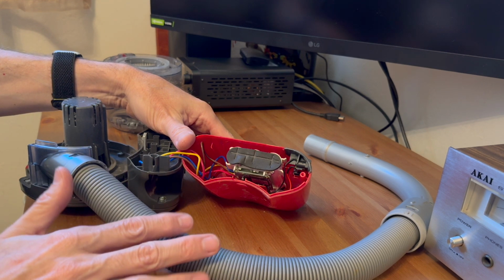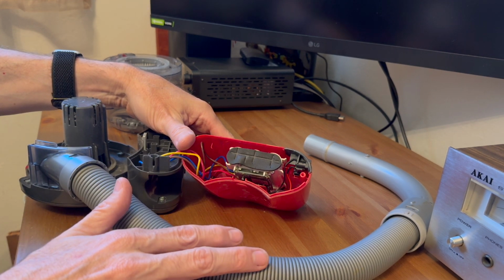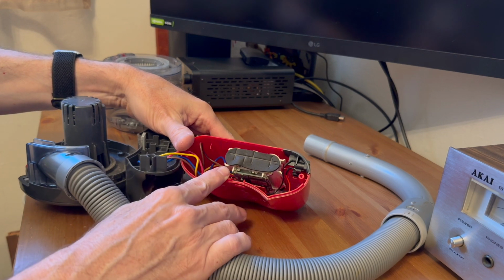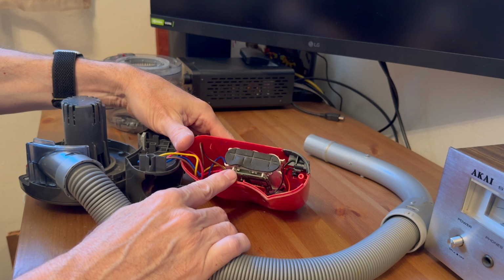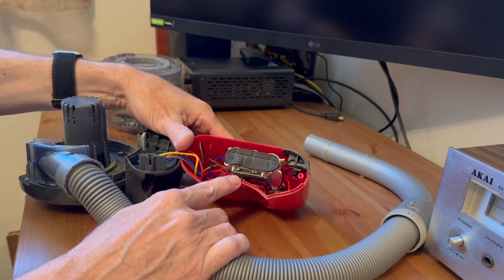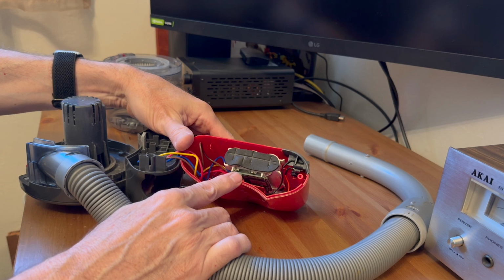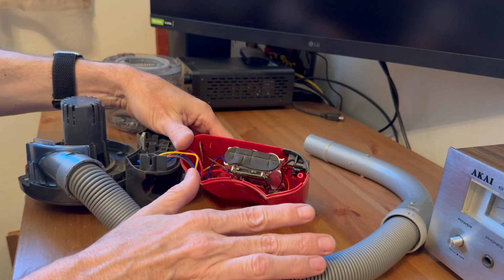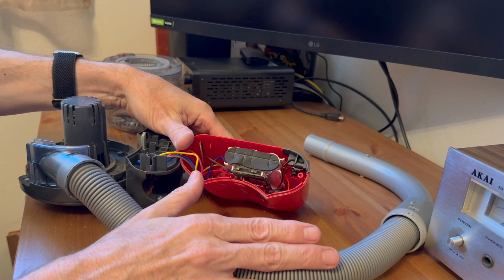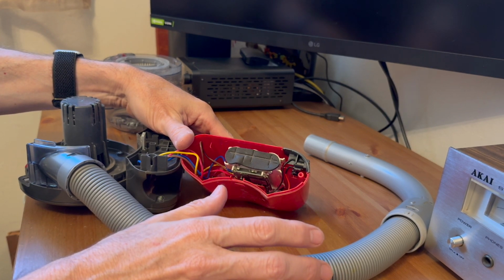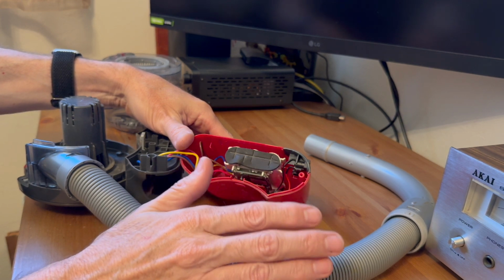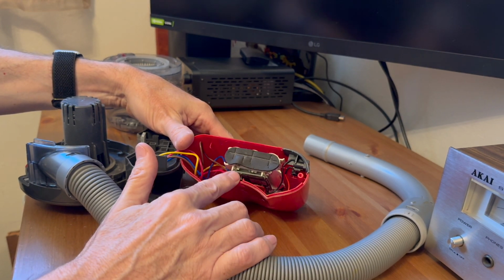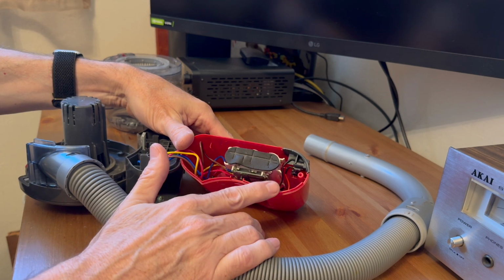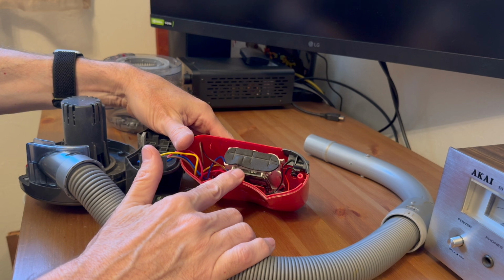What I found over time is that these things get what's called out of balance, meaning one of the batteries either charges or discharges too much. When one of the batteries exceeds either the lower or the upper threshold of voltage, the whole power gets disabled and turned off. It's not like using regular AA cells where one is a little weaker but you'll still get power through. The battery management system will disable all of the voltage if any one of the 3 batteries exceeds or goes below the thresholds.